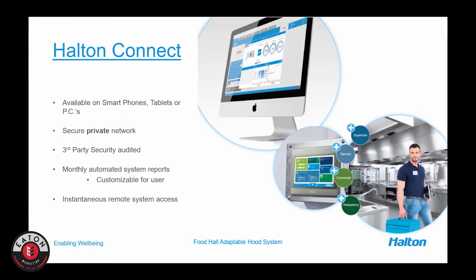Obviously, that would be based on the tenant lease agreements, but there are some very unique capabilities with this. One very important aspect is remote access to the systems. If we ever have trouble on a given application, we can dial into that system and make changes from a remote location and potentially address some problems, or at least put a system in an override until we can get a service tech on site.